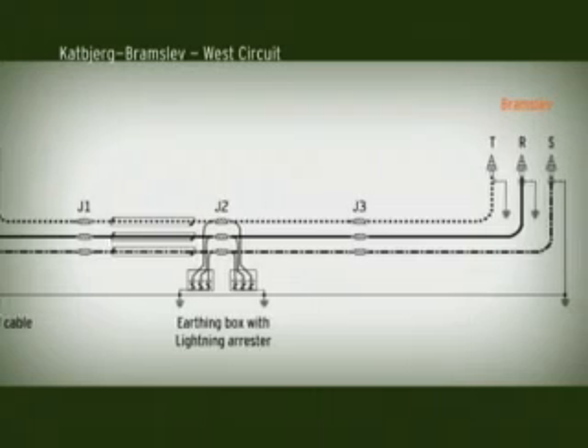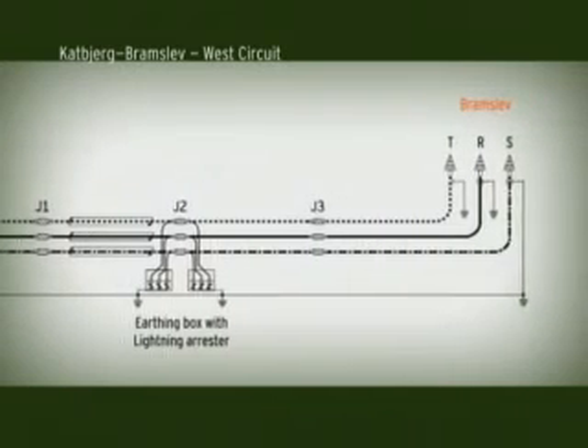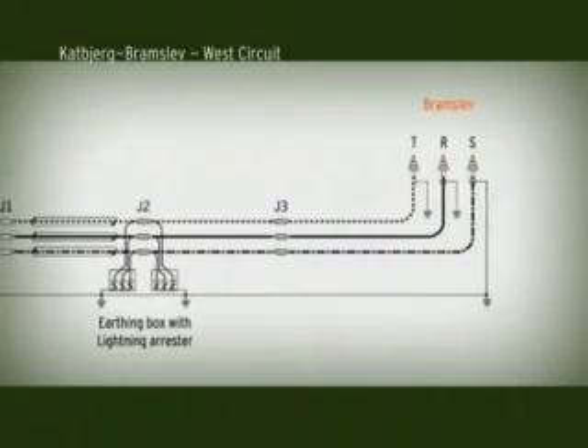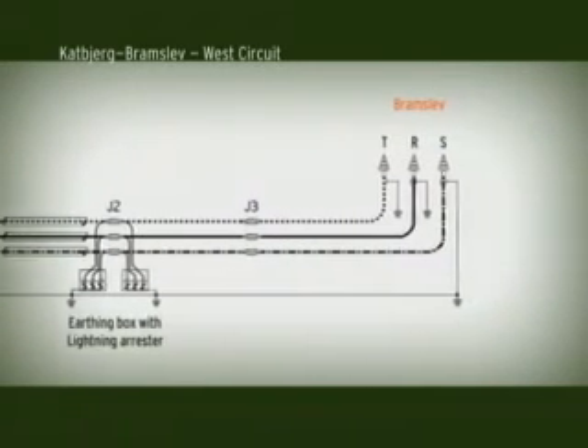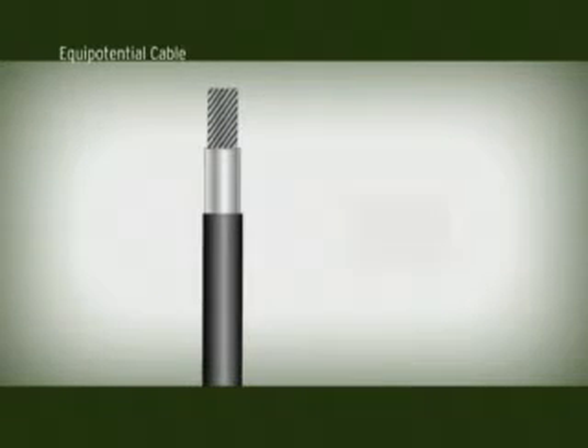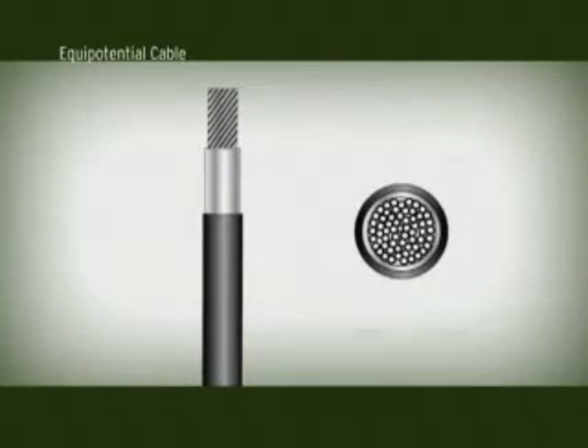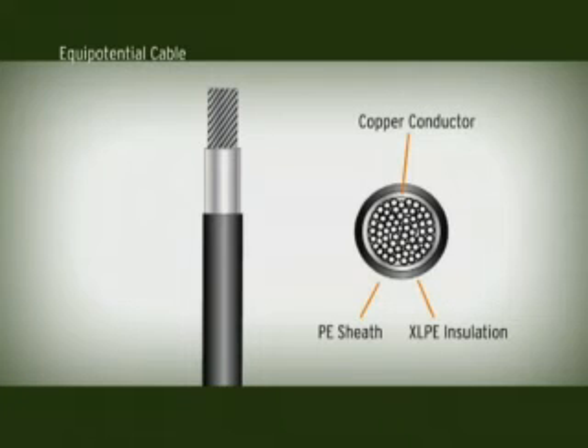The Katbjerg-Bramslev section has 3 joints in all. Joints numbers 1 and 3 are joints without shield interruption. A continuous earthing cable is laid together with each circuit, which reduces the zero-sequence impedance of the circuit. The earthing cable is earthed in the Katbjerg and Bramslev transition compounds. It is also earthed at joint number 2, where the cable shields are earthed via surge arresters.